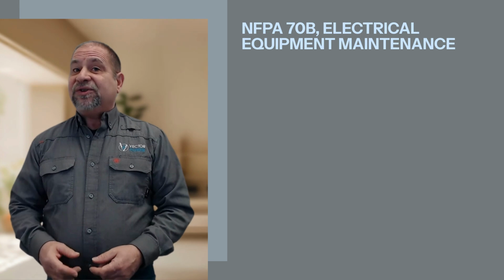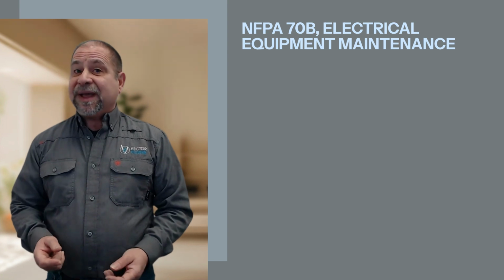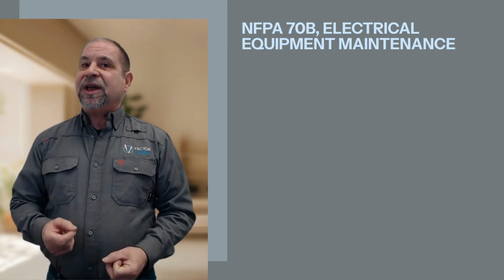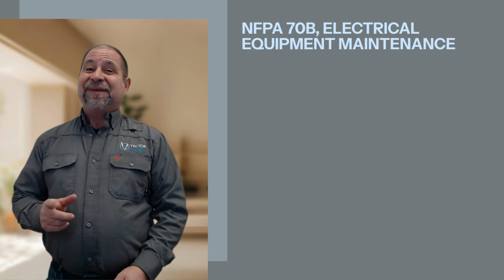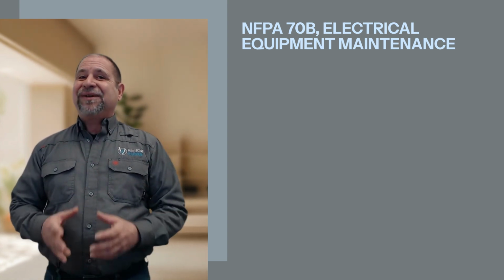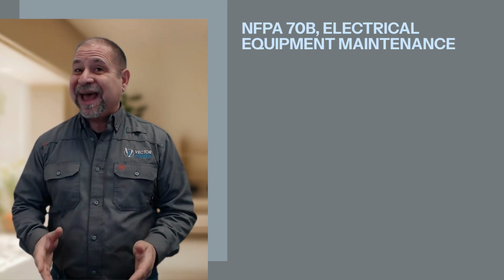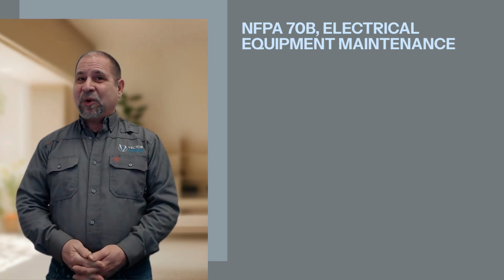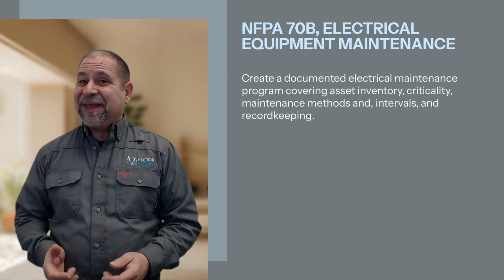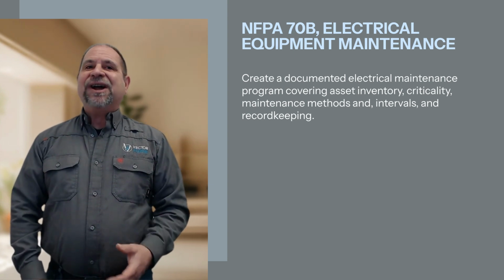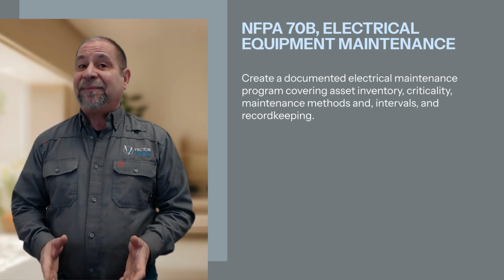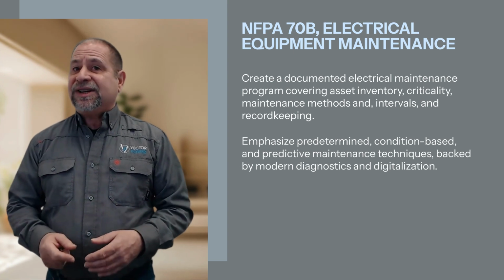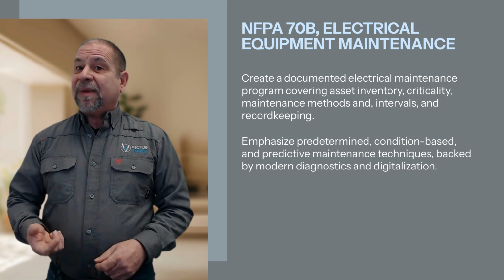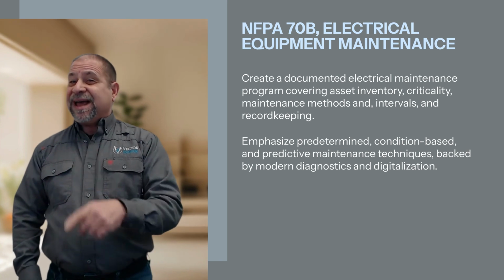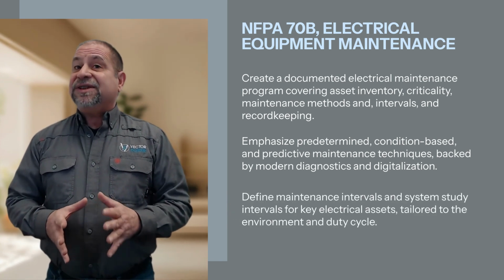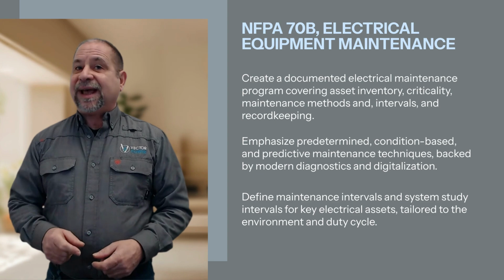NFPA 70B, electrical equipment maintenance. NFPA 70B, updated effective January 2023, transitioned from a recommended practice to a mandatory standard for electrical equipment maintenance. It now lays out requirements for establishing and maintaining an electrical maintenance program, EMP. Core themes include: create a documented electrical maintenance program that covers asset inventory, criticality, maintenance methods, intervals, and record keeping. Emphasize predetermined, condition based, and predictive maintenance techniques backed by modern diagnostics and digitalization. Define maintenance intervals and system study intervals for key electrical assets tailored to the environment and duty cycle.